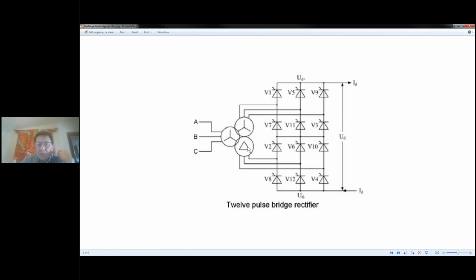So, phase shifting those, we'll explain the reason why we do that in a second, results in the fact that the voltages on this winding and the voltages on this winding don't correspond from a phase standpoint. They're out of phase. They're phase shifted. You dare not connect these 2 outputs. However, once we go through a full wave bridge rectifier, they can be connected on the DC side. Now, this is a 12-pulse bridge rectifier that has the diodes in series.